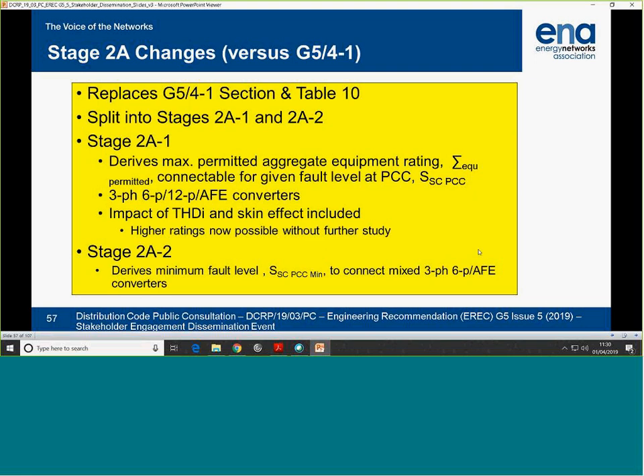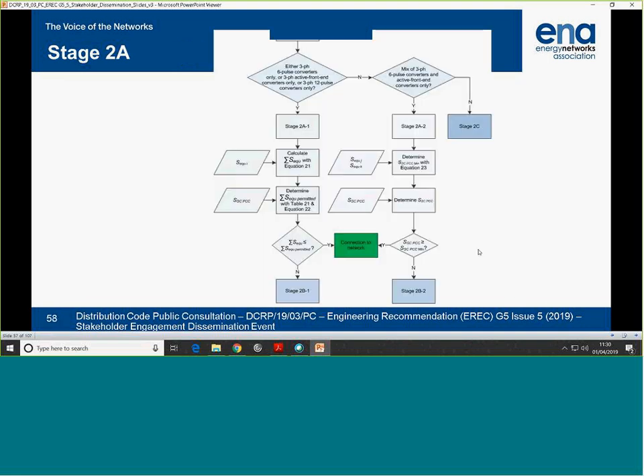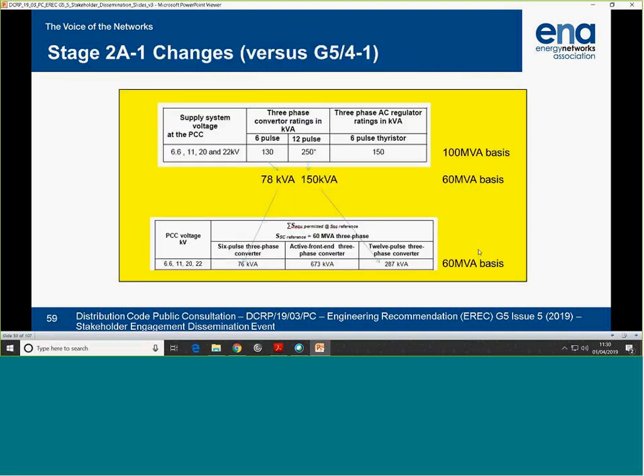I'll summarize it, but basically it splits into 2 parts, 2A1 and 2A2. So this just mirrors what we had for stage 1C. Rather than go into all that detail, just go ahead a little. You'll see what I mean. This was old G5/4, this was called table 10 at the top. The old values were on a 100 MVA basis. The new ones are on a 60 MVA basis, and that's because it was thought that 100 was just too high. A lot of networks were never going to be at 100. A lot of networks are more like 50 MVA as a fault level basis. So we went for 60.